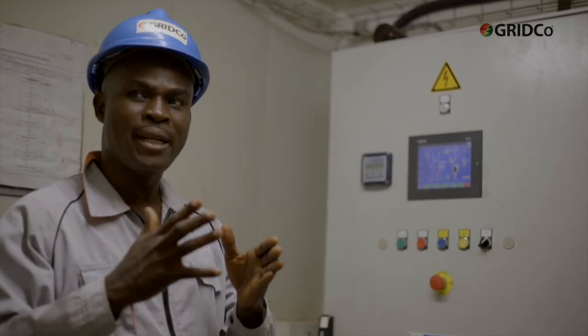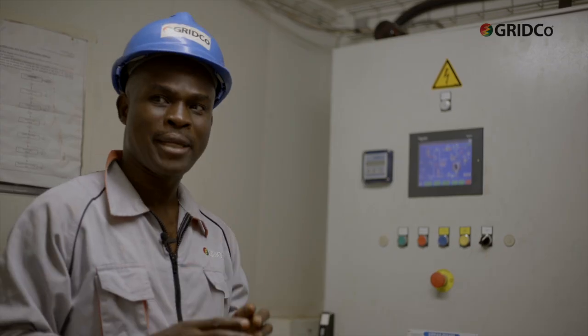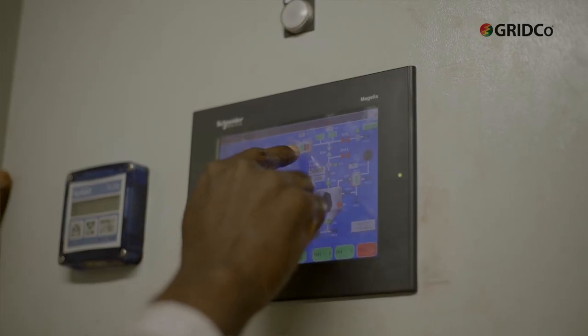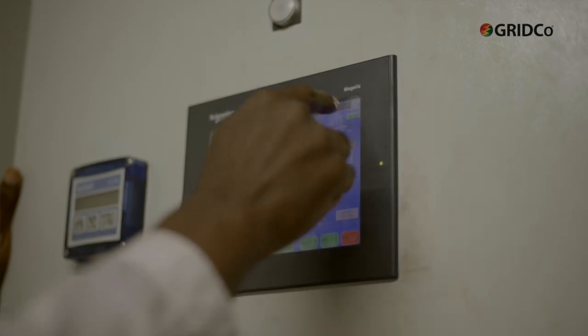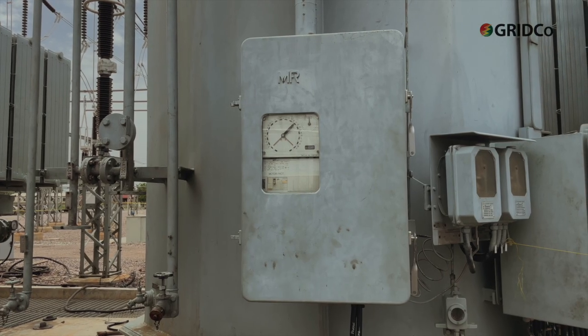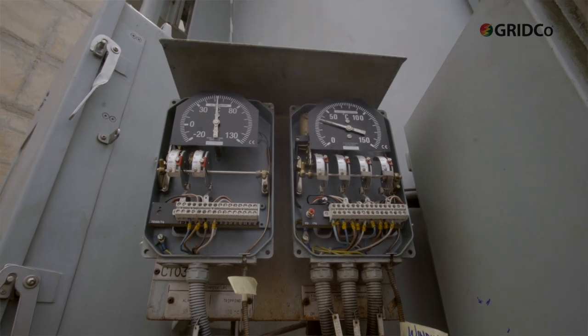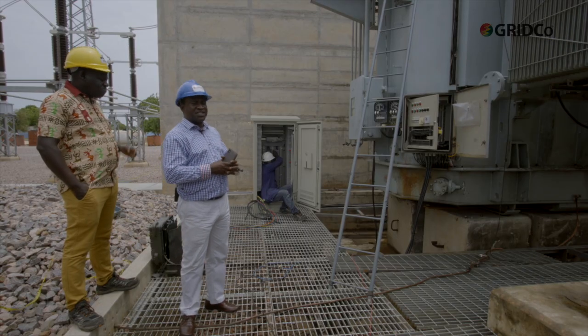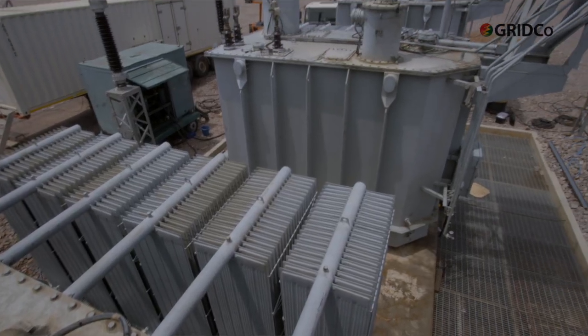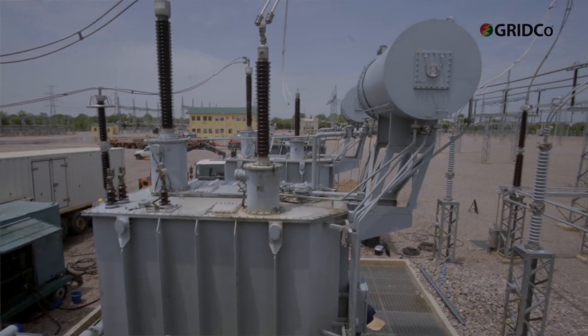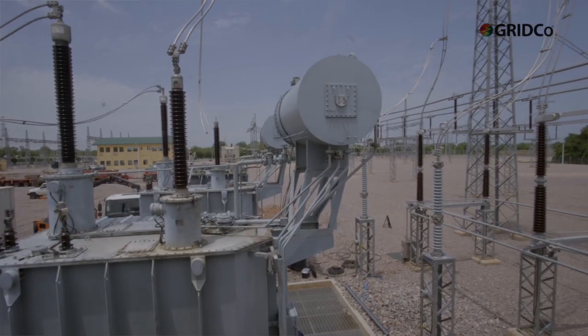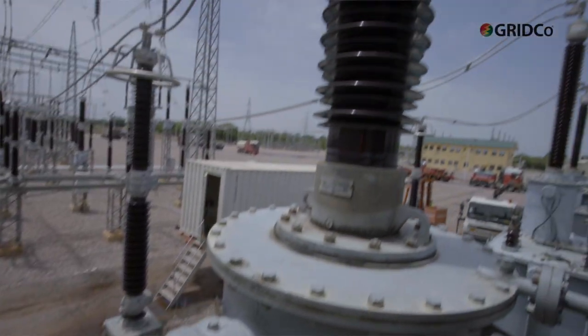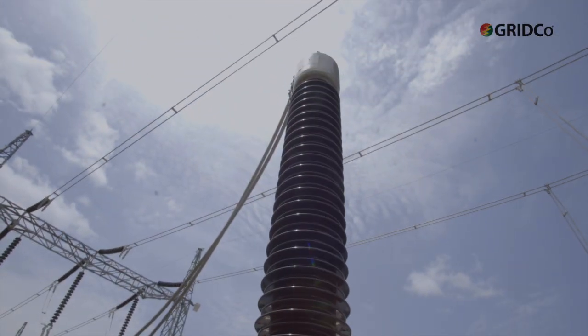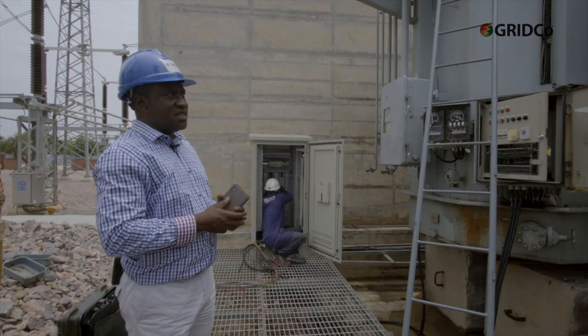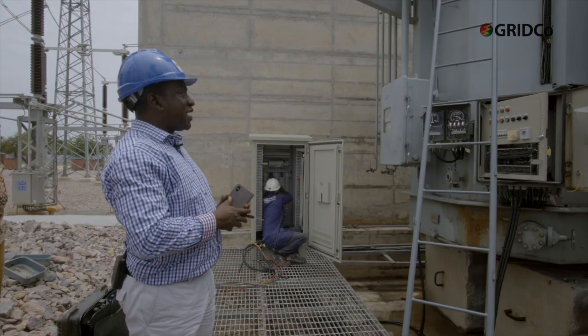This is so crucial because any moisture that is entering into the transformer has capacity to increase the transformer temperature. And the number one enemy of a transformer is basically its temperature rise. Each transformer has two thermometers, one for monitoring the temperature of the winding and one for monitoring the temperature of the oil. The transformer by transformation is made out of windings, and the windings are made out of copper. The copper has a resistance. So anytime you push current through the copper, meaning the customer connected to the 225 section is drawing up load, current will automatically flow.